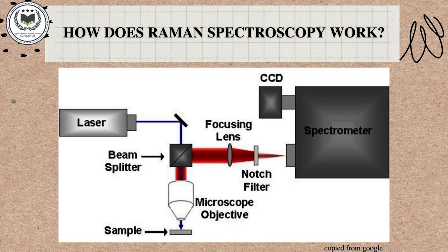After the laser light has irradiated the sample, the scattered light is passed through a filter to get rid of any light from the excitation laser. Then it is directed onto a grating, which distributes the inelastic parts like a prism according to wavelength. At the end, these rays are directed to a CCD sensor, which then outputs a spectrum depending on the intensity.